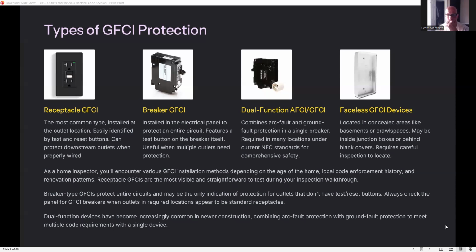So your GFCI receptacle, my understanding is that it's going to last anywhere from 8 to 10 years. They can obviously go longer. The older ones, you're going to find that they freeze up and don't trip in the proper manner. The GFCI breaker will last longer. I don't tell people it's more reliable, I just say it's in the panel. You've got to go downstairs to reset it if the panel's downstairs, but it will last longer. Dual function GFCIs, I don't run into those a lot. And of course the faceless. Okay, let's keep going here.